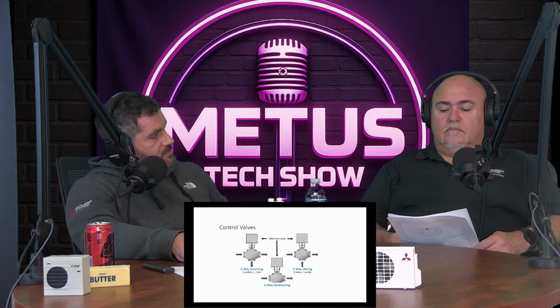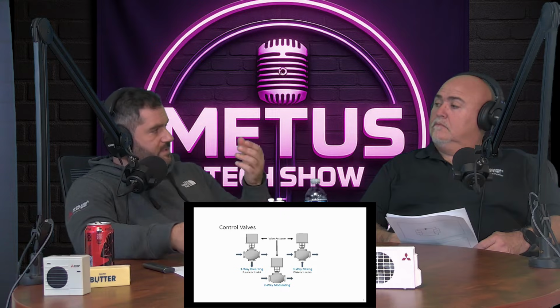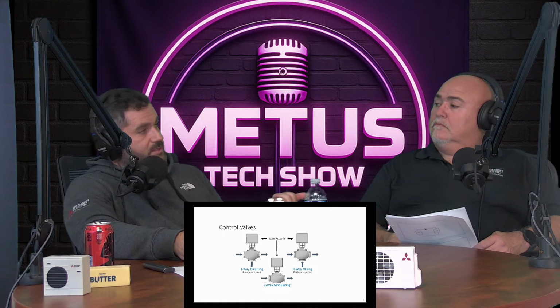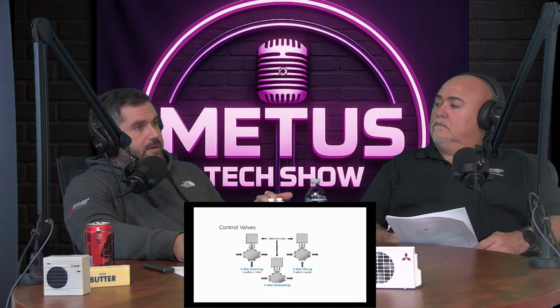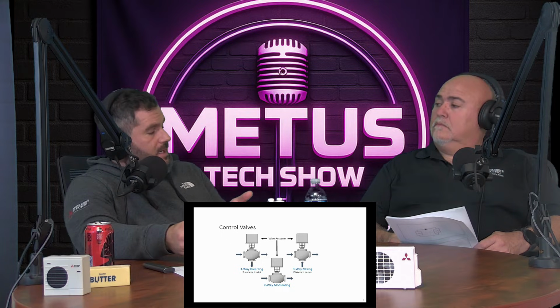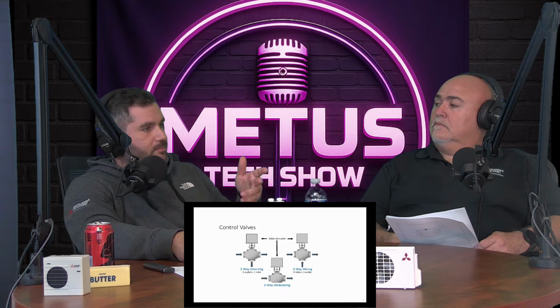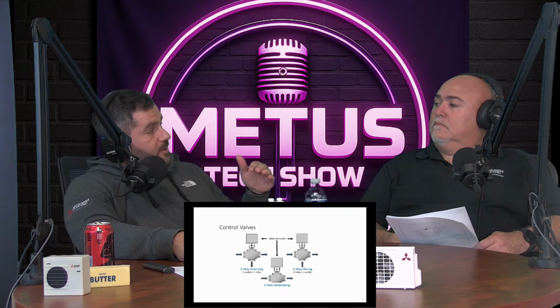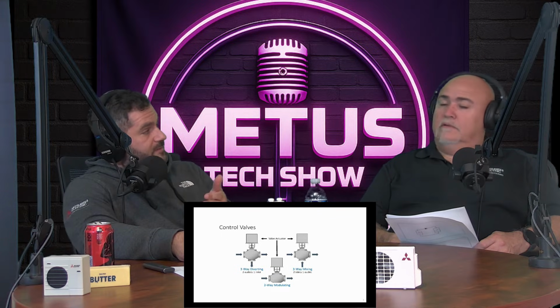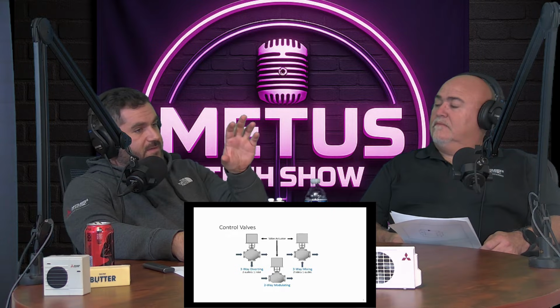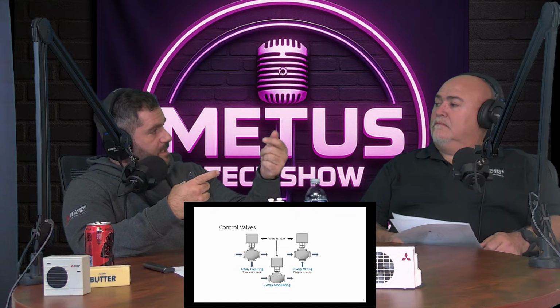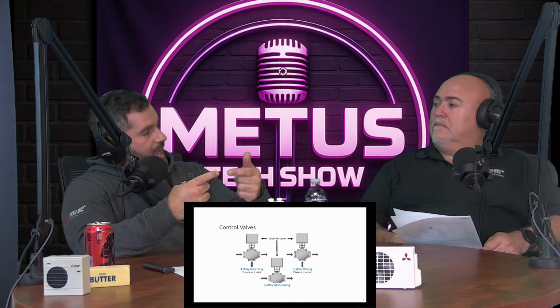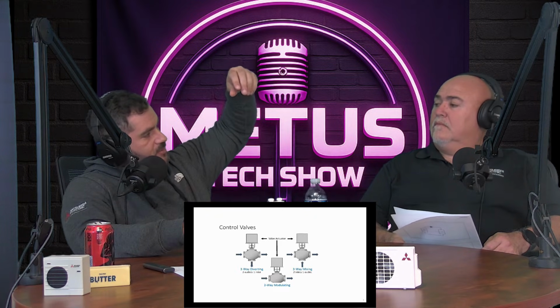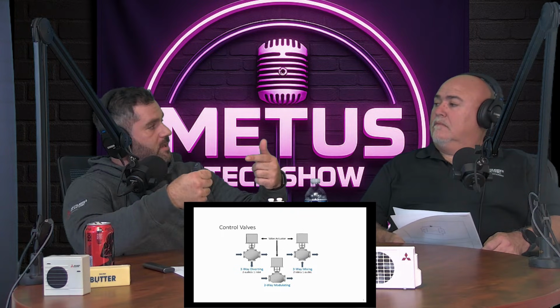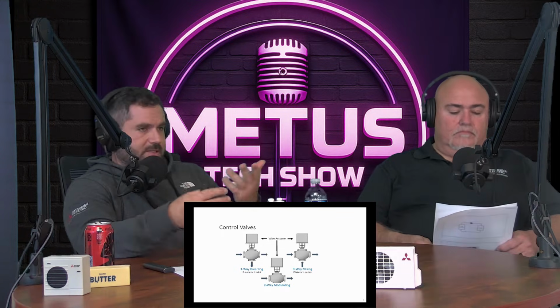There are three-way mixing valves, where we're actually taking in two inlets to give a single outlet. Now, this is really common, like you were talking about, on a tankless coil or most water heaters, where you may store your water at 140 degrees just to prevent Legionella, which is a bacteria that grows in low or medium temperature water. You may want to store it at 140 to make sure you kill it. The problem is you don't want 140 degrees going to your faucets. Right. So coming out of your water heater, you'll put in this mixing valve. One of the inlets is that 140 degree water. The other inlet is just cold city water coming in the other side. And then the outlet is what actually goes up to your faucets, and you have a dial that you can set your actual outlet temperature. All it's really doing is changing the ratio of that 140 degree water and city water to make sure that we get, say, 120 degrees going out to the faucets.